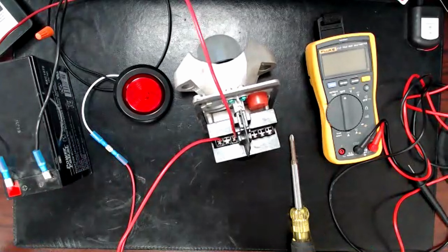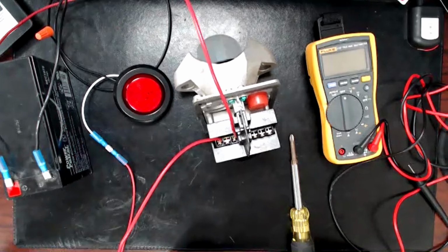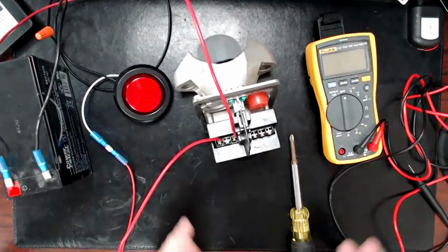Wiring it in series would mean that it goes up one side of the circuit, wire nuts over to the other, hits the other device before returning to the panel. So if you had a bad junction somewhere or the wire got cut or broken somewhere, both parts of the circuit would actually stop working there.